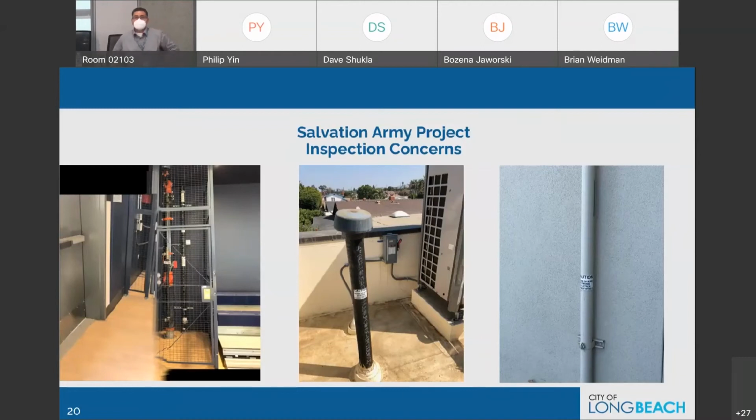And from here, I'd like to direct the attention to the pipe on the right. This vent is installed on the outside of the structure, which is anchored according to the plumbing code, Table 313.3. Any mechanical venting system should be supported horizontally and also vertically according to the plumbing code. With this, I go back to David, to the PowerPoint.